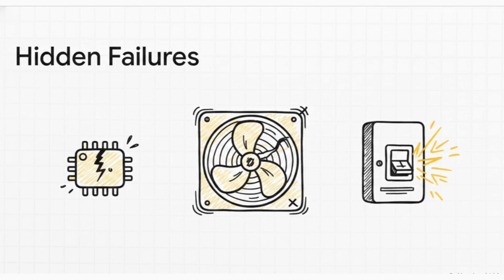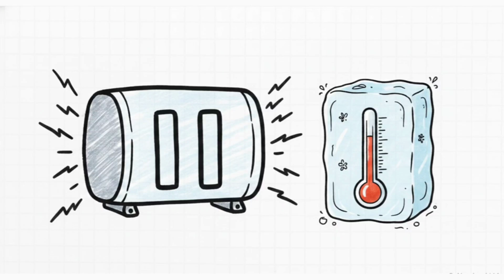Let's break these down. A defective temperature sensor brilliantly illustrates one of the most confusing problems you can face. The AC turns on. The compressor constantly tries to start. You hear that deep hum kick in, and then it immediately stops. Click. Silence. This is very often just a rogue temperature sensor. It's a cheap, super easily replaceable part, but when it fails, it completely confuses the entire compressor cycle. It basically tricks the machine into thinking the room is already freezing cold, so it just shuts off prematurely.